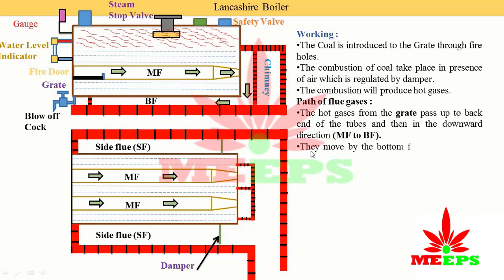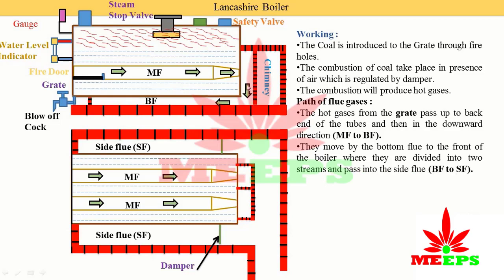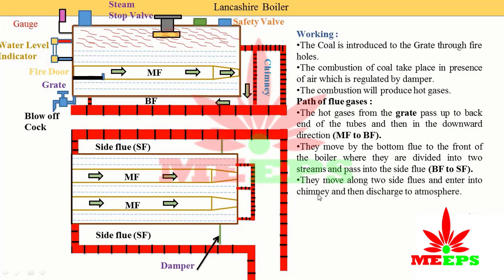From the back end of the tubes, the gases move in a downward direction — main flue to bottom flue. The bottom flue then carries gases to the front of the boiler. At the front of the boiler, the gases divide into two streams, one on each side, and pass into the side flues — this is the transition from bottom flue to side flue.